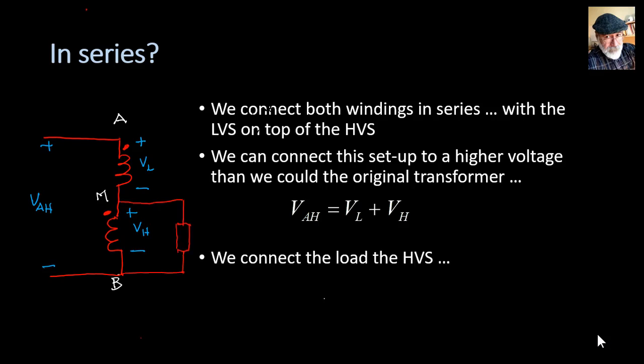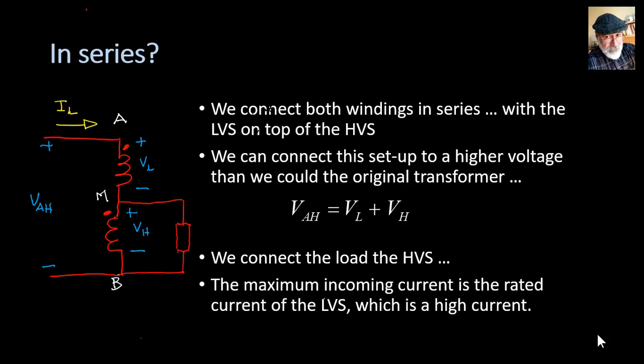And now we connect the load to the high voltage side, to VH. The maximum incoming current is the rated current of the low side. Why? Because that current IL will flow through that winding. Of course, it cannot exceed the specifications of that winding. So the maximum current I can feed into the whole arrangement coming from the left is the rated current of the low side.